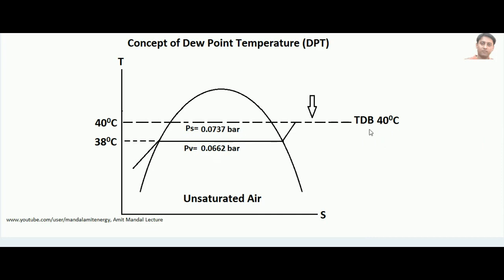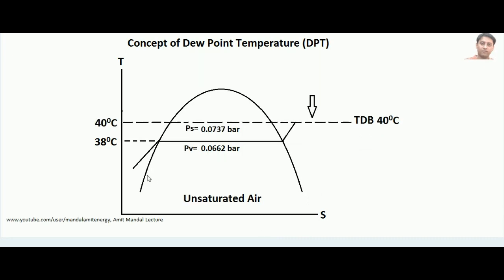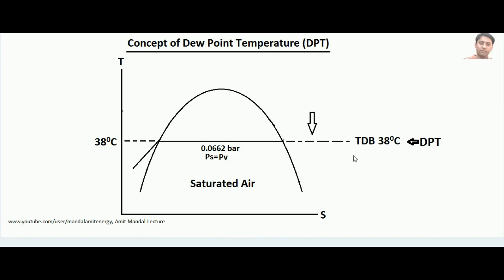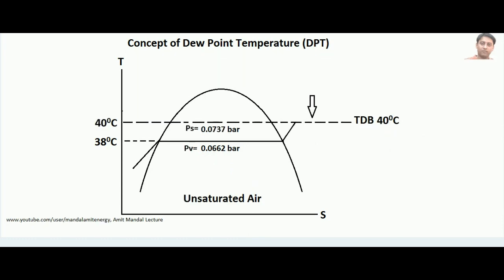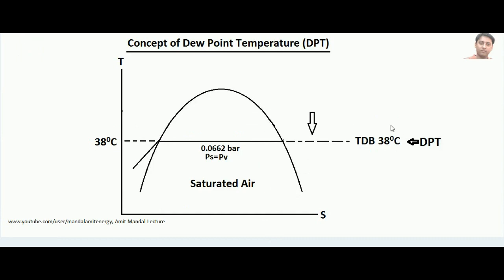If the vapor pressure is lower than the saturation pressure of the corresponding dry bulb temperature, the air is unsaturated. Now suppose I reduce the temperature from 40 degrees to 38 degrees centigrade. At 38 degrees centigrade, the vapor pressure matches the saturation pressure — air is now saturated. I have lowered the temperature to the level where the vapor pressure in air equalizes the saturation pressure of that lower temperature. This temperature is the dew point temperature.